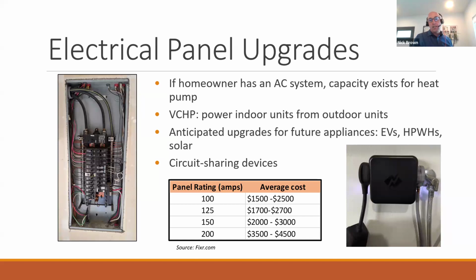If you do have an existing home that only has heating, then yes, you may need additional panel space to go to heat pump. Because as we said earlier, you'll need the circuit for the outdoor unit, and the indoor units in the variable capacity equipment are powered from the outdoor units.